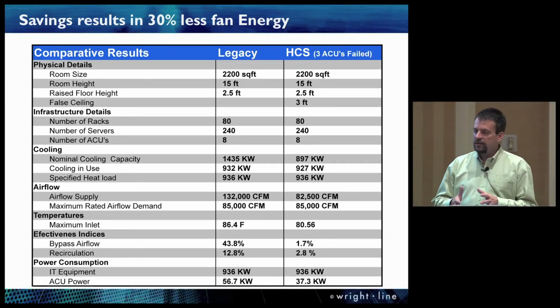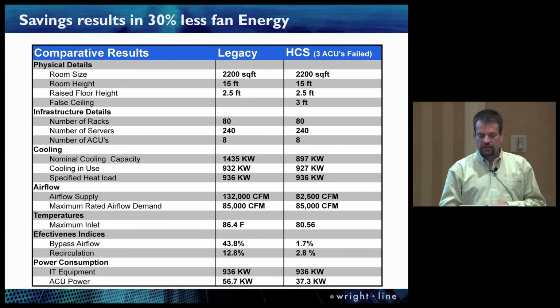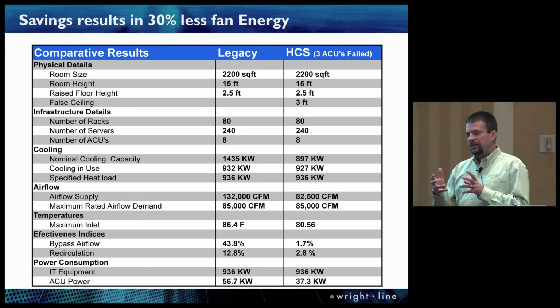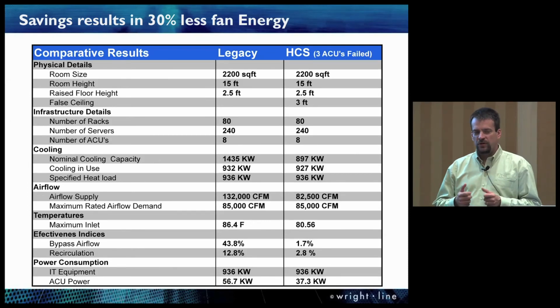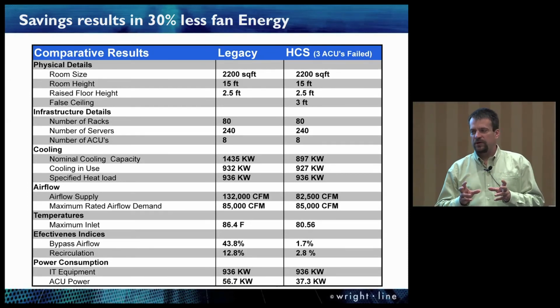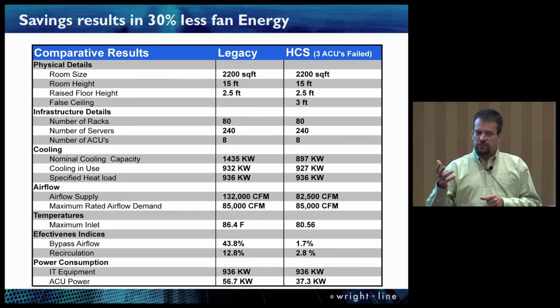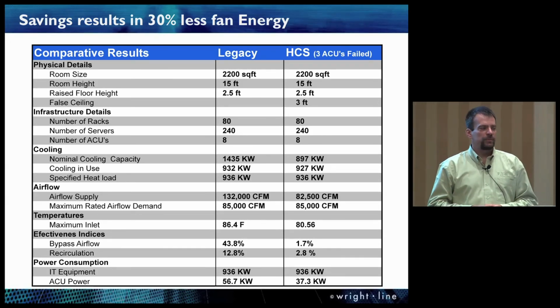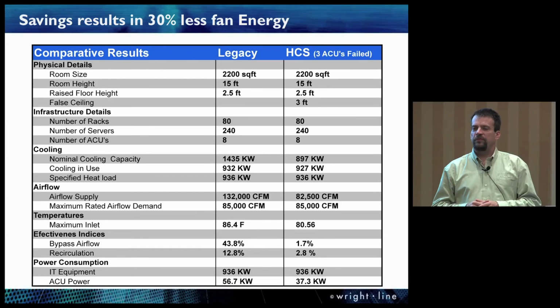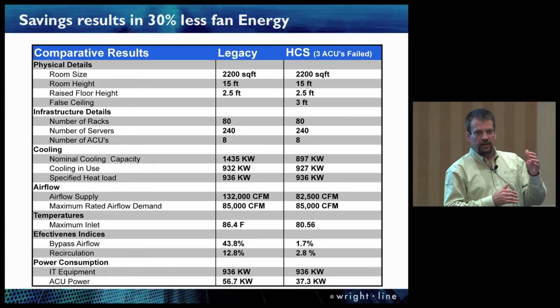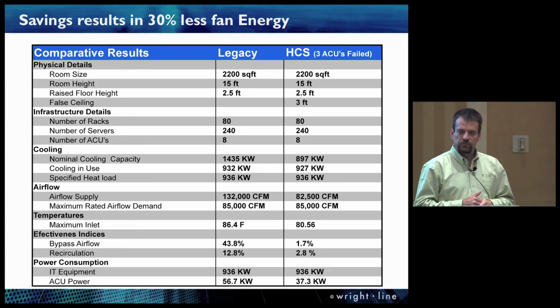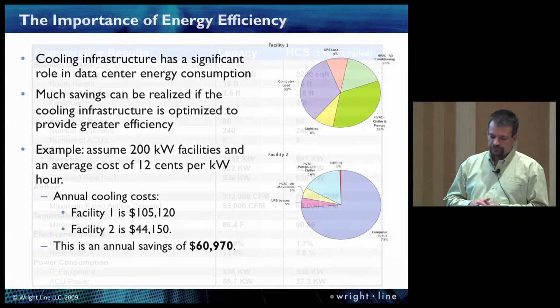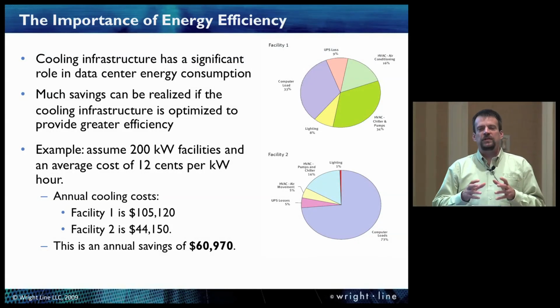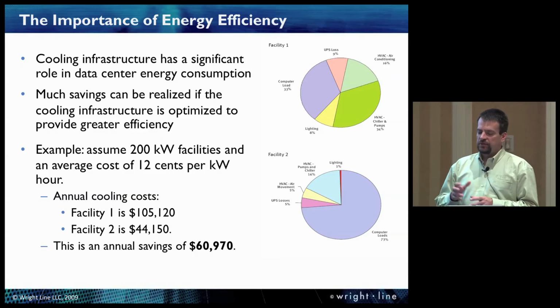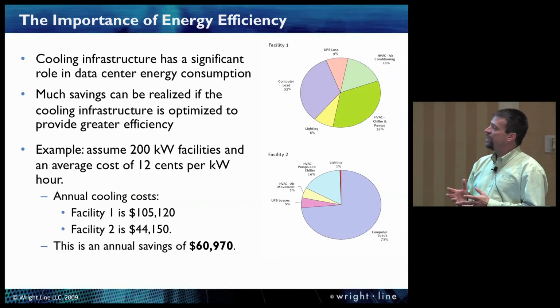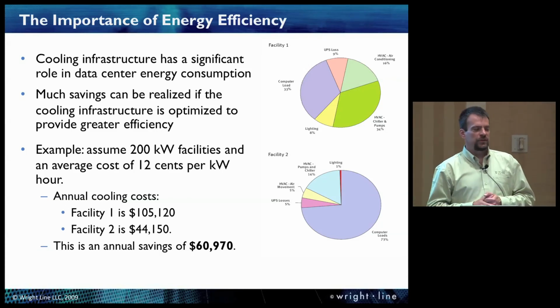So ideally, that's the capture, that's the efficiency that is available for anyone looking at a containment strategy to adopt: capture that type of waste, the difference between that 85,000 demand and that legacy oversupply of 135,000 CFM. And that fan energy to move that air is really what you're saving. How does that work out? This is just a typical example of some of the efficiency and the different pieces of the pie that consume energy in a data center.